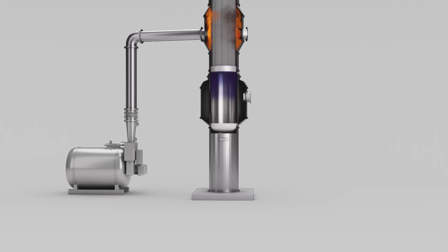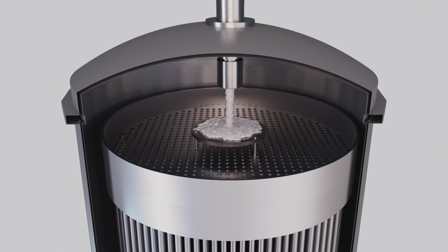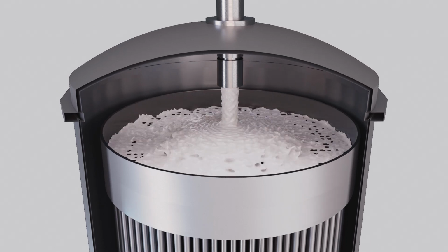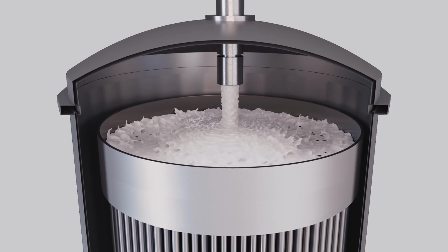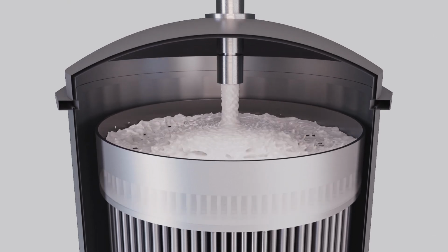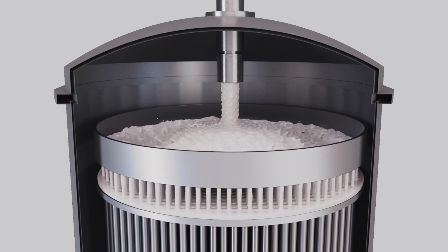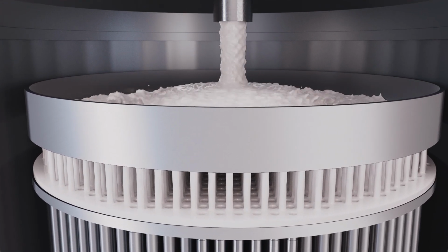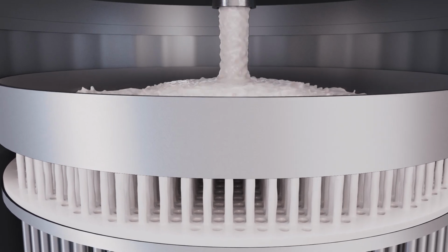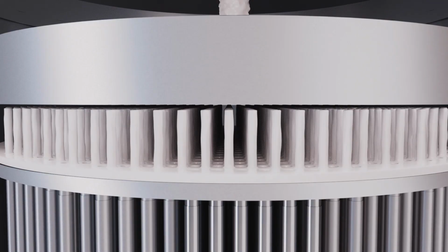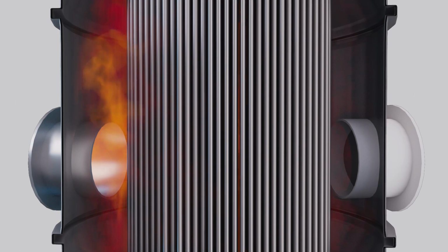To separate the product to be concentrated from other constituents in the water, energy must first be applied. This takes place in the heater chamber. The medium to be evaporated is introduced into the evaporator intake and spreads over a distributor plate onto the tube bundle. From here, it runs down against the inner walls of the tubes as a thin film under surface tension and gravitation. The medium is heated up by introducing water vapor into the heater chamber.